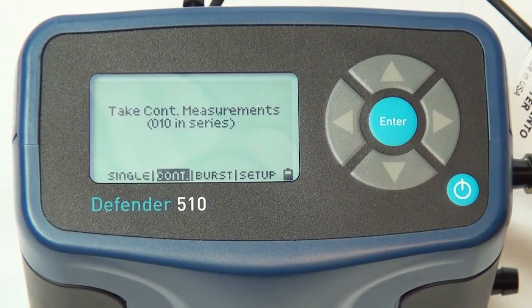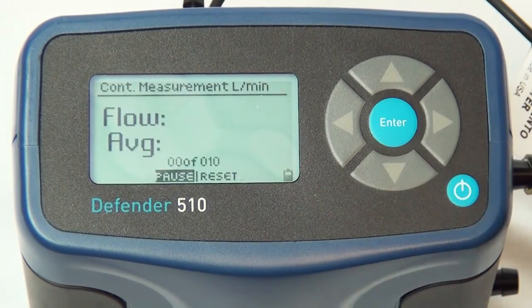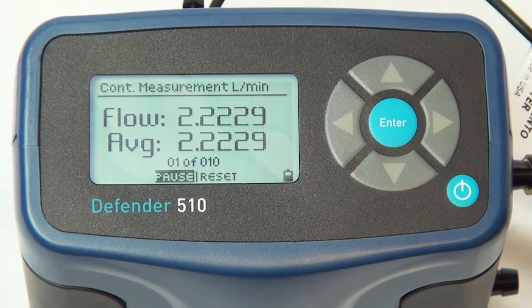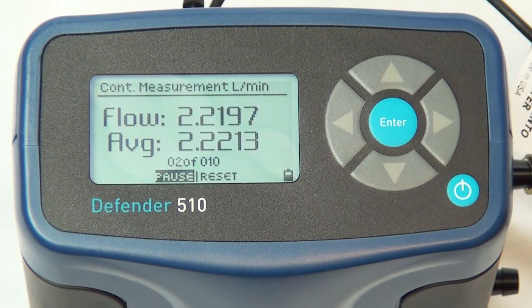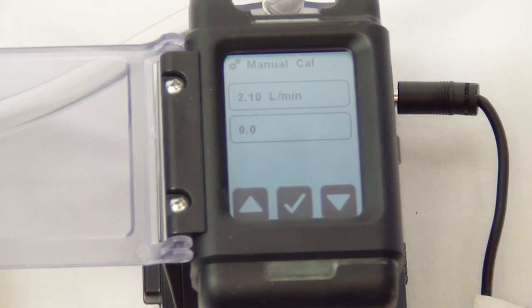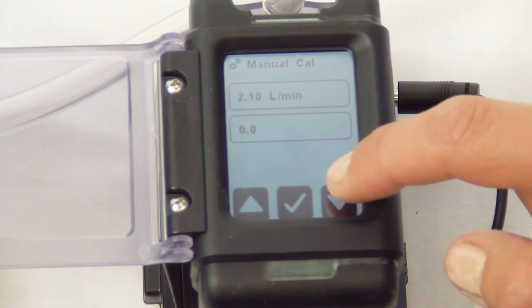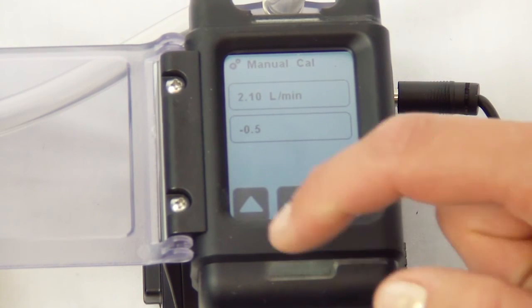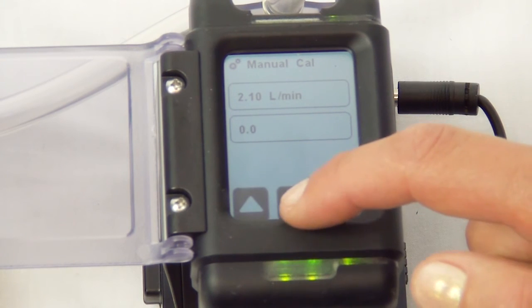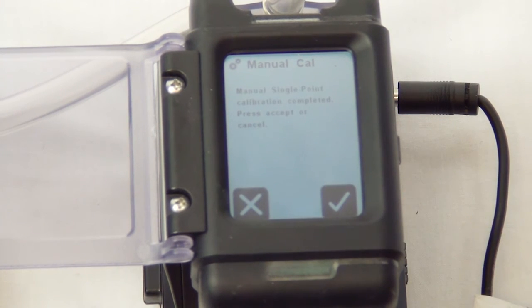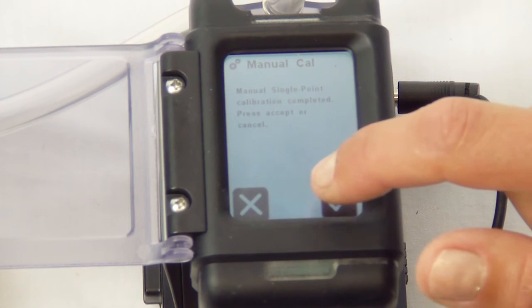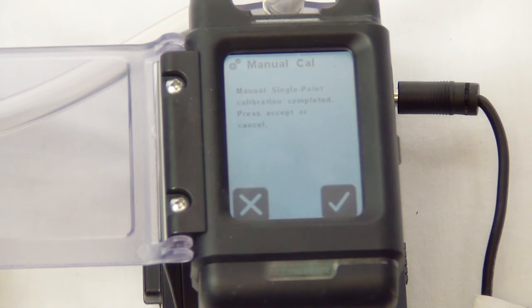While the pump is running, compare the pre-designated flow rate on the SKC touchscreen to that of the flow rate displayed on the Defender. If the flow rates differ, adjust your SKC pump by pressing the up or down arrows to the correct flow rate. When the flow rates match, press the check mark button. To accept the calibration, press the check mark again. To cancel, press the X button to be brought back to the home screen.